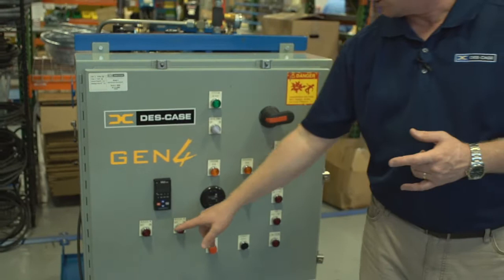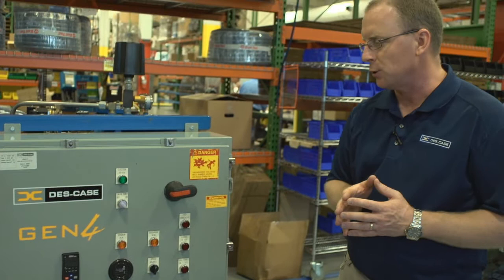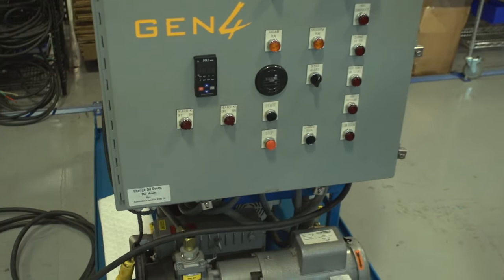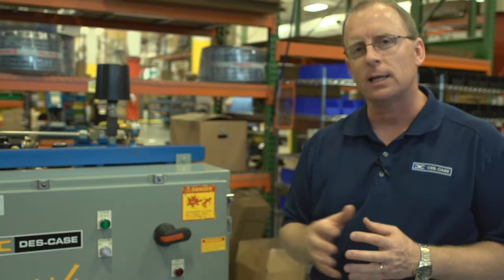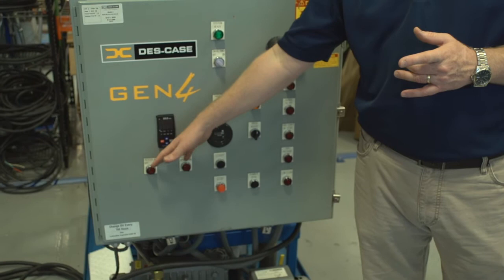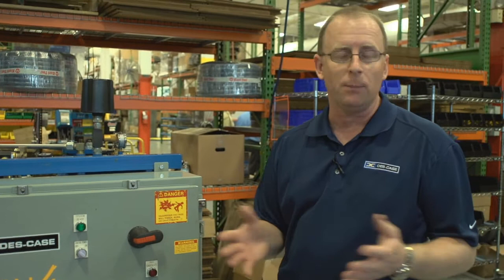We also have heater selector switches, and you'll notice on this unit it has two heater selector switches. That's because this unit is designed for use on energized transformers and in substations. This unit is a 240-volt single-phase unit, and because station power can sometimes be limited, Des-Case splits the heater into two, allowing you to select either heater and if need be, not consume as much electricity.